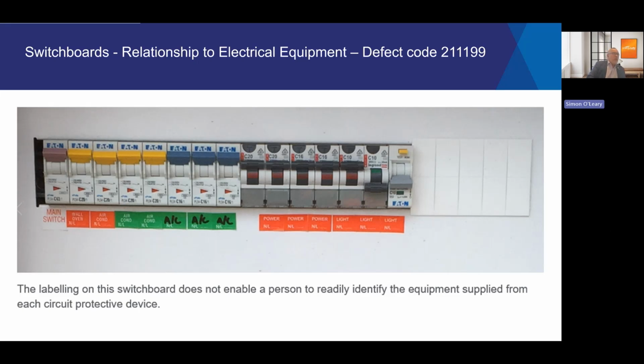Labelling of switchboards. The wiring rules say that the switchboard should be labelled so that the operator of equipment can identify what part of the electrical installation the individual circuit breaker or switch controls. I'll set aside the power and light for a moment. I just wanted to focus on the 6 air conditioners installed. It's important that the circuit breakers are labelled correctly because particularly with air conditioners, that can be equipment that is worked on by non-electricians, so they don't clearly have a way to test that the electrical equipment may be isolated, and it may be just for mechanical maintenance, such as replacing a fan blade.